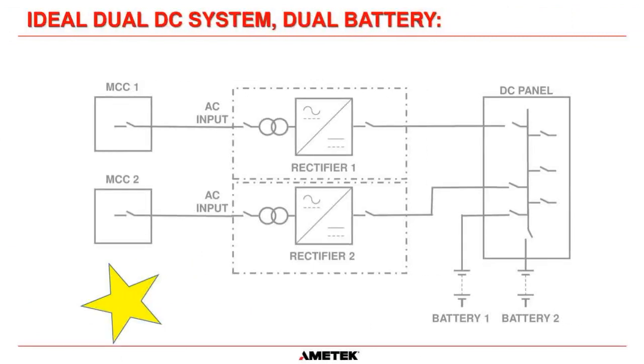But you can see on this drawing here, this is the Gold Star Award, because they have connected 2 chargers in parallel, going through individual disconnects here to the DC panel, but they've also connected 2 batteries with their own disconnects here. Okay, this means that if battery number 2 fails, you can open this disconnect here, remove the battery and replace it, and you still have battery backup from battery 1, and you still have 2 chargers feeding the load.